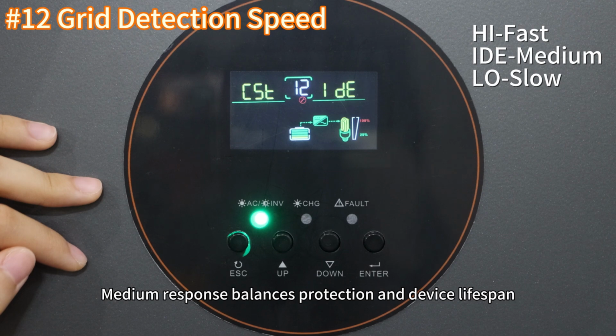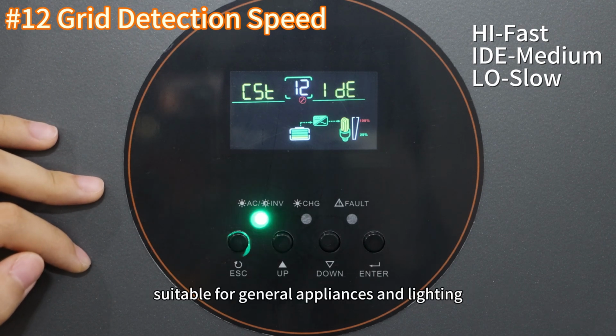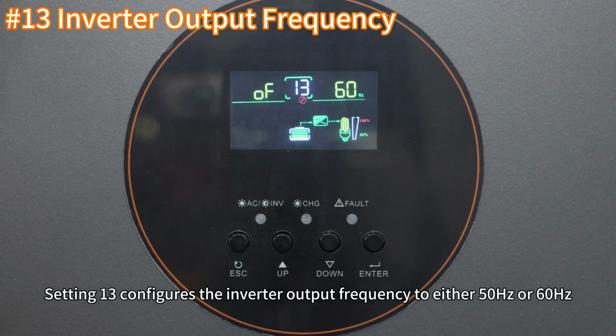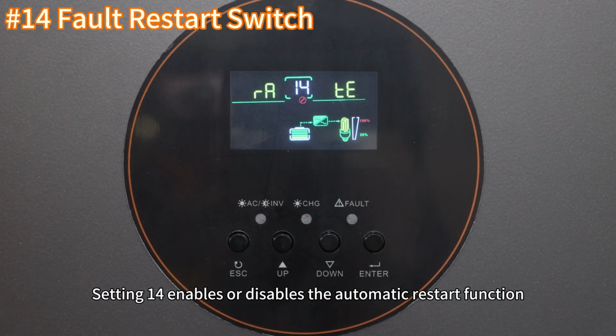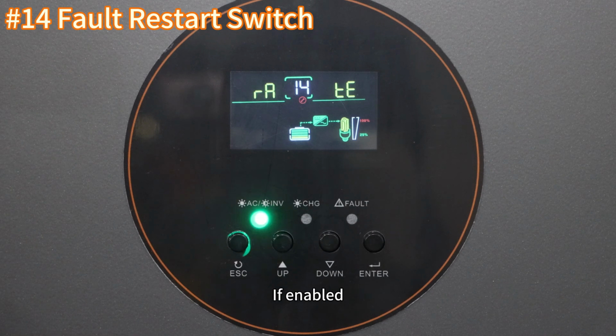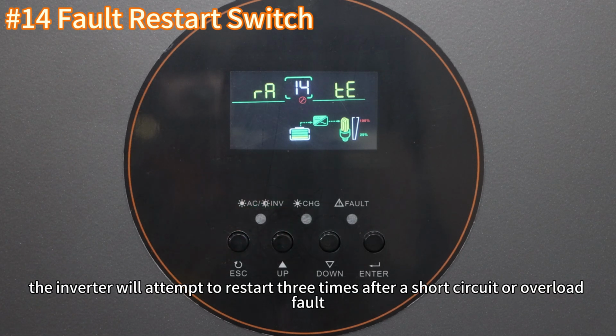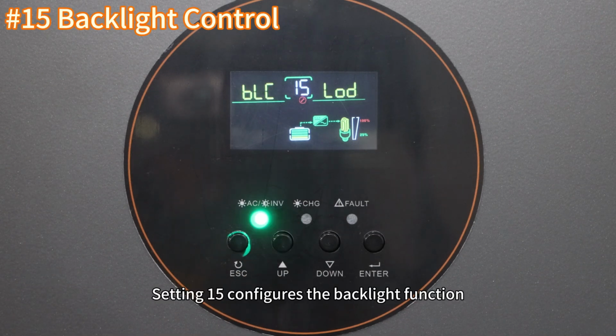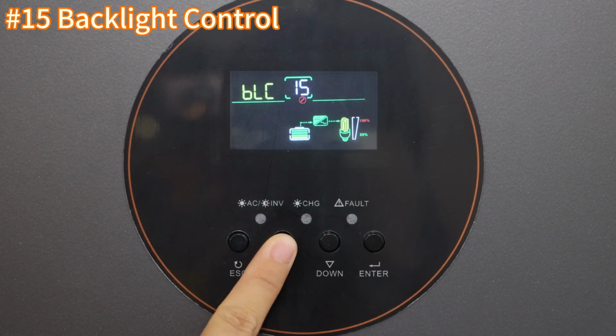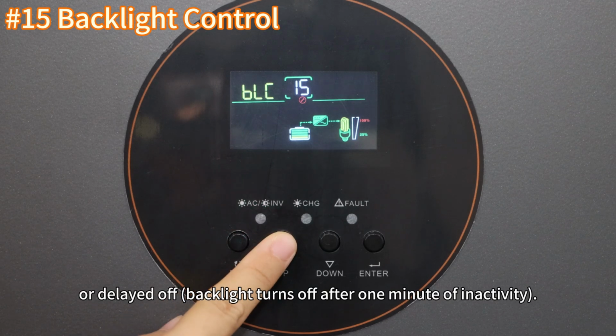Medium response balances protection and device lifespan, suitable for general appliances and lighting. Setting 13 configures the inverter output frequency to either 50 Hz or 60 Hz. Setting 14 enables or disables the automatic restart function. If enabled, the inverter will attempt to restart 3 times after a short circuit or overload fault. Setting 15 configures the backlight function with options for always on, always off, or delayed off.